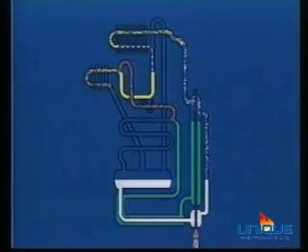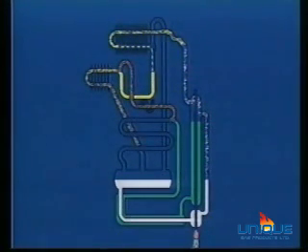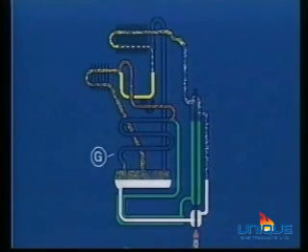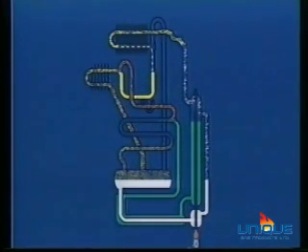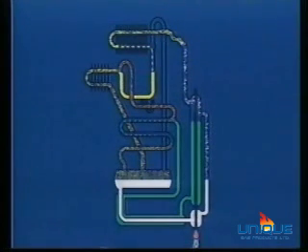After the evaporation, the ammonia gas with the hydrogen is heavier and it goes down pipe I by gravity. They reach the tank and rise immediately to pipe G, which is the absorber. The poor solution — that is, the water condensed at the start of the process in the pre-condenser — goes down through the same pipe.